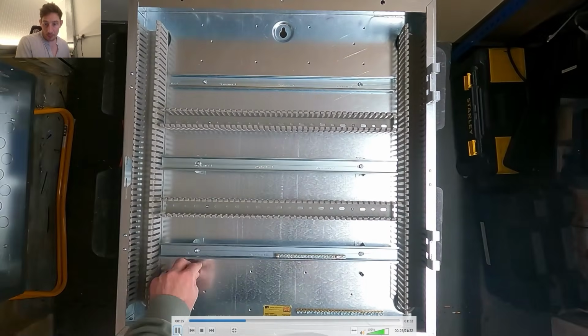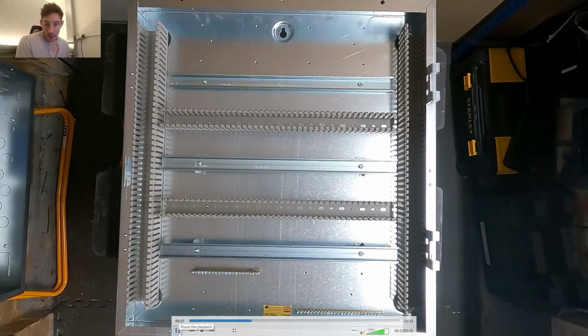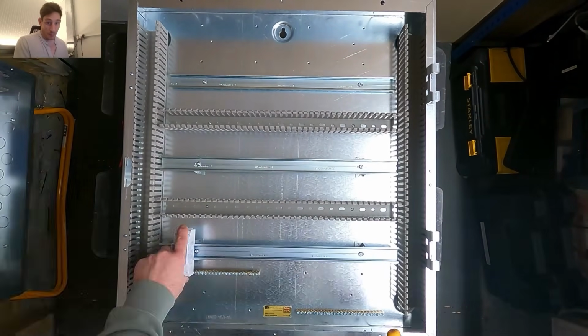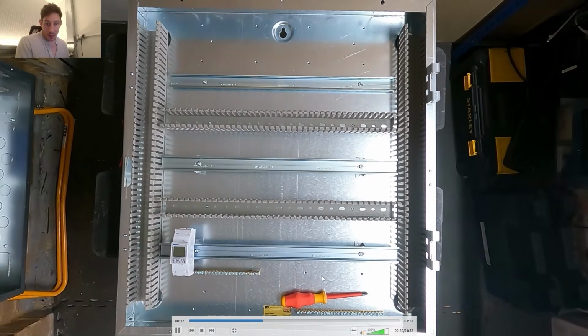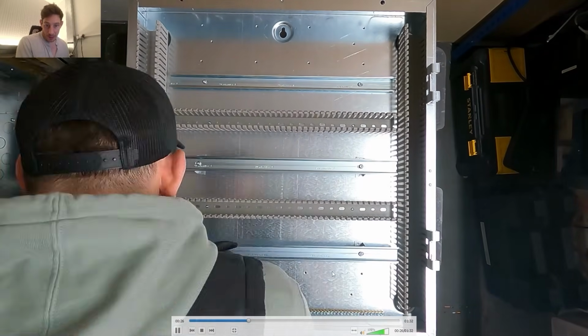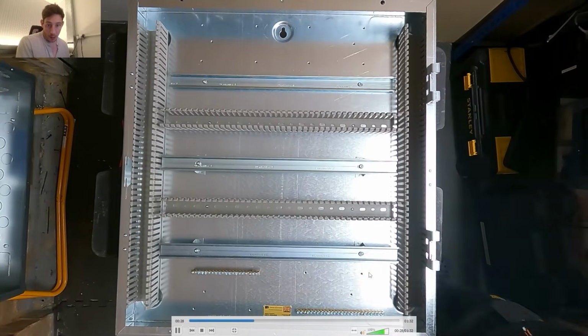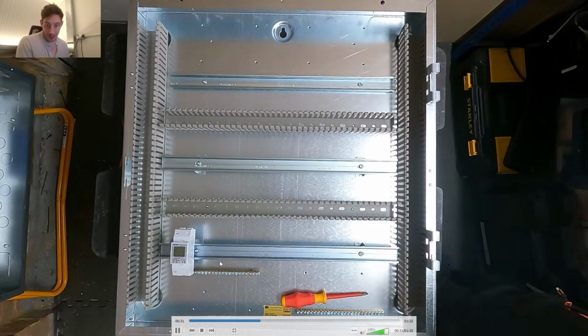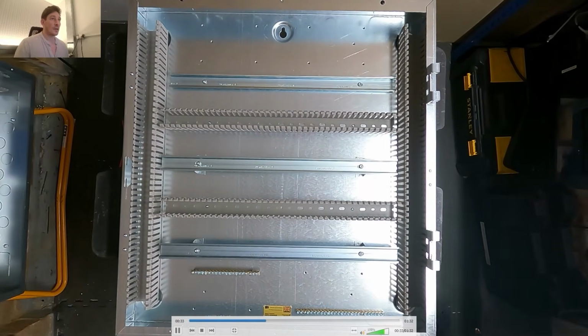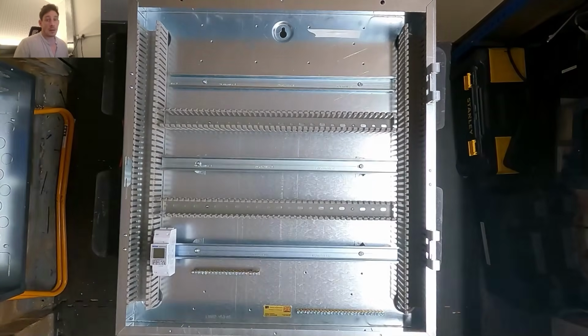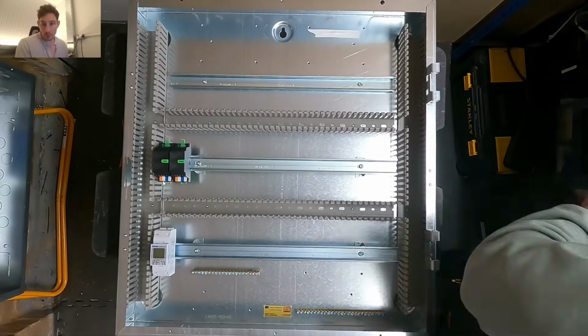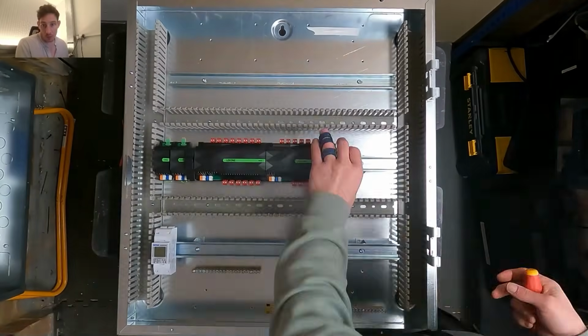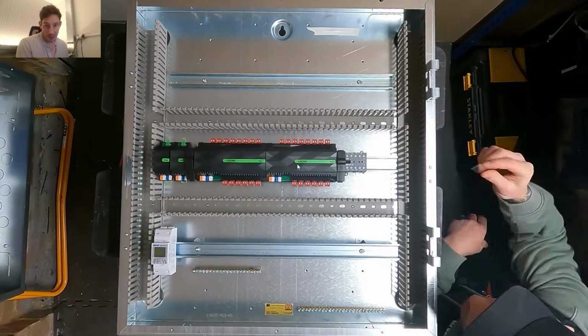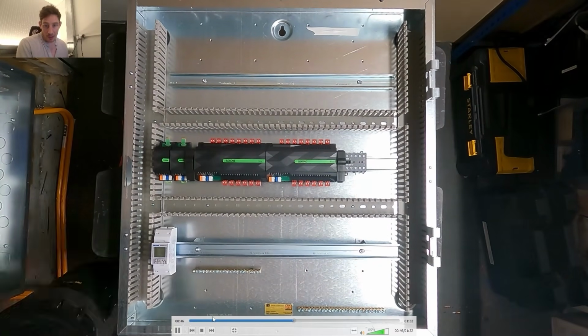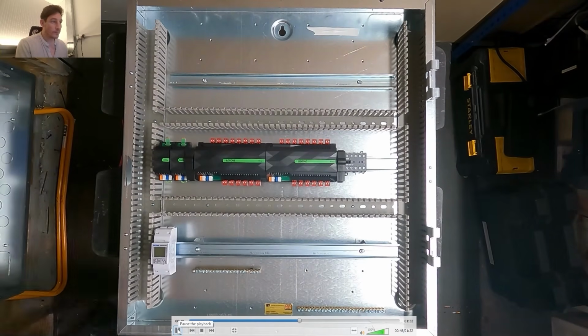Okay, off we go. So straight away you can see that I removed the top DIN rail. For the terminal blocks, it's top cable entry on this panel, and then you saw back there that I just moved the neutral bar to this side because this is where the RCBOs are going to go. And then we've got our energy meter, our Modbus and one-wire extensions, relay extensions, and then a contactor for our immersion heater.